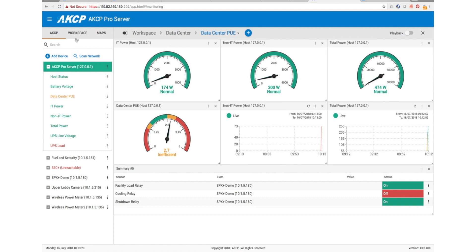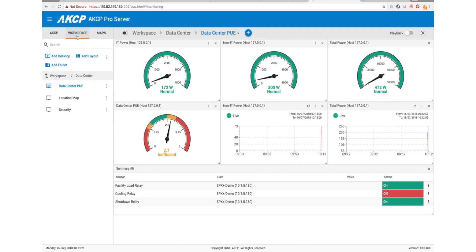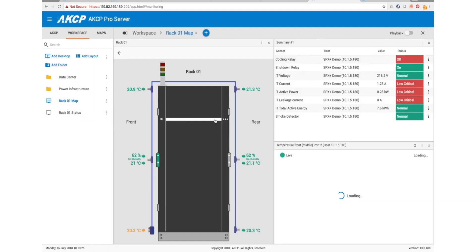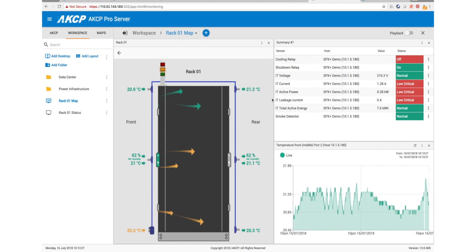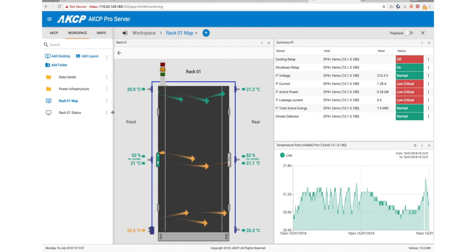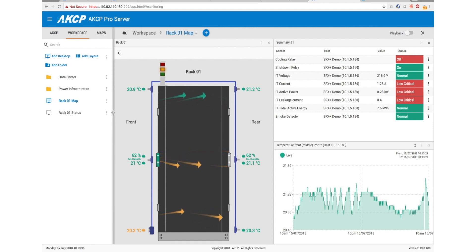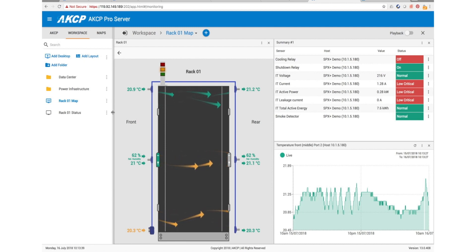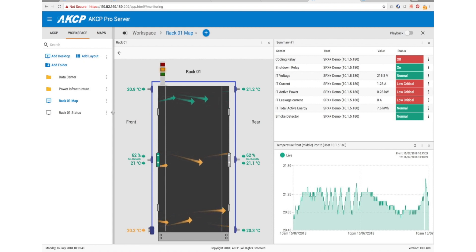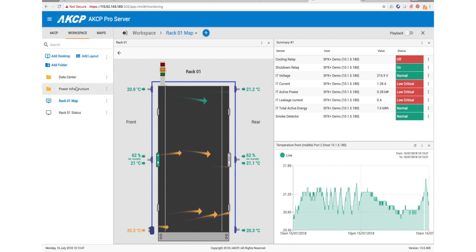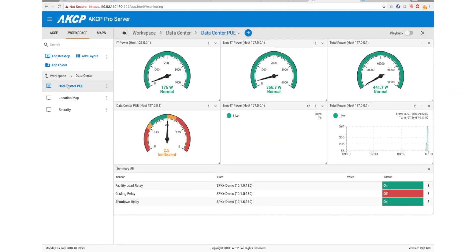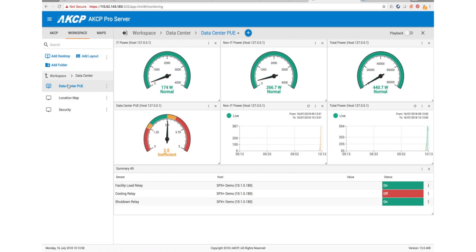In order to get the rack maps, I have another video where we already cover that, where we can set up the rack maps with AKCP thermal map sensors so you can accurately monitor the temperature inside each one of your cabinets. Then we can begin to tweak your data center settings, the amount of cooling and non-IT load that you're using to get that PUE number as low as possible, while at the same time ensuring that we're not going to exceed any of the maximum temperatures for our servers. I hope you found this video useful. Don't forget to subscribe to the channel and I'll see you next time.